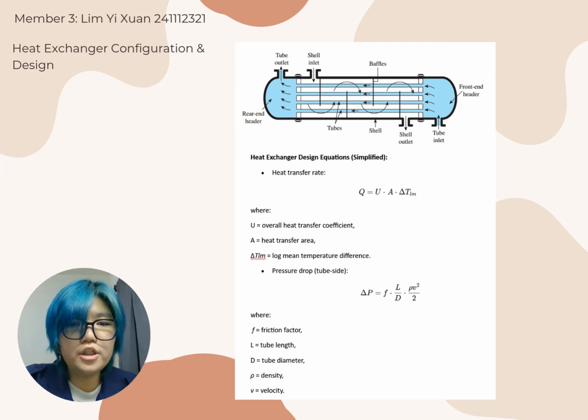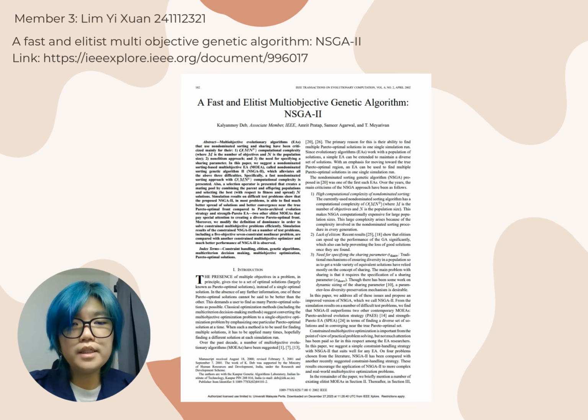Three shell and tube heat exchangers are used. Economizer preheats seawater, a boiler generates the steam, and a superheater raises the steam temperature to 362.5 degrees Celsius. And then next, the key constraints include the minimum 20 Kelvin pinch point and exhaust back pressure above the 100 kilopascal, turbine pressure from 40 bar to 0.3 bar. The system is optimized to maximize the power output while minimizing cost and weight. A multi-objective genetic algorithm NSGA2 is used to find the best trade-off by adjusting number of tubes, tube size, and exhaust gas conditions.